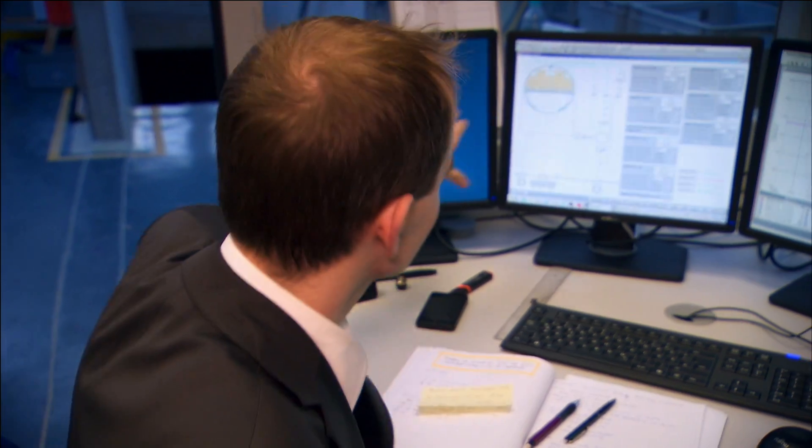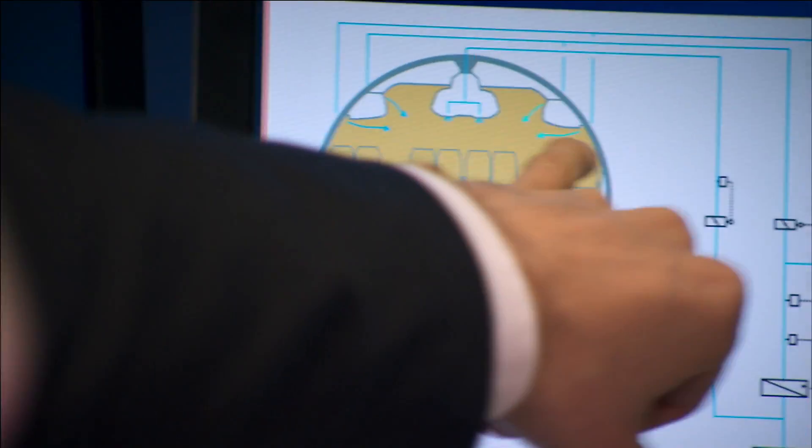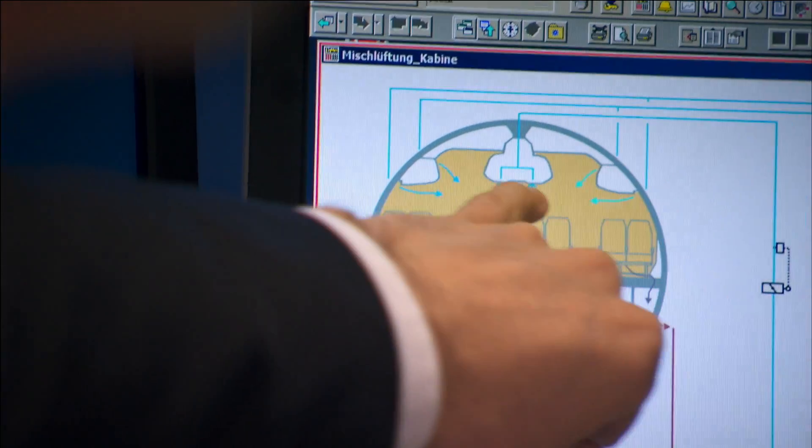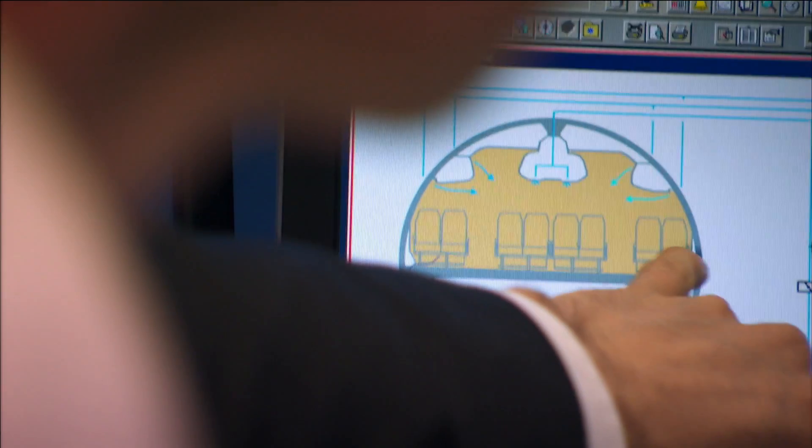A little smoke helps to highlight the gentle air movement. We usually try to develop in the aircraft cabins a cross-sectional movement of the airflow. So when you look at the sketch, for example, we supply the air at the very top, it hits the overhead bin, circulates down, and is extracted at the bottom. We can see this circular movement in the test cabin.